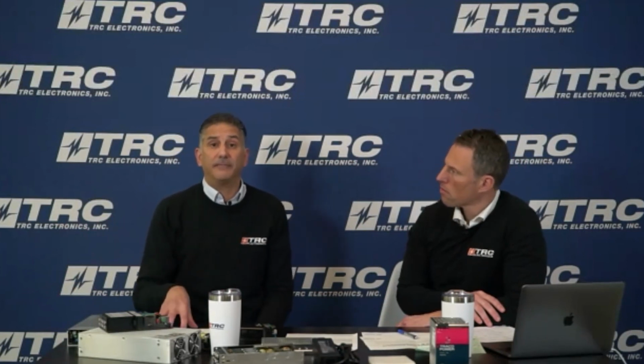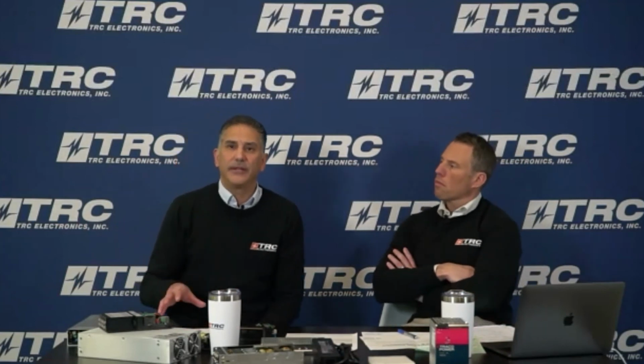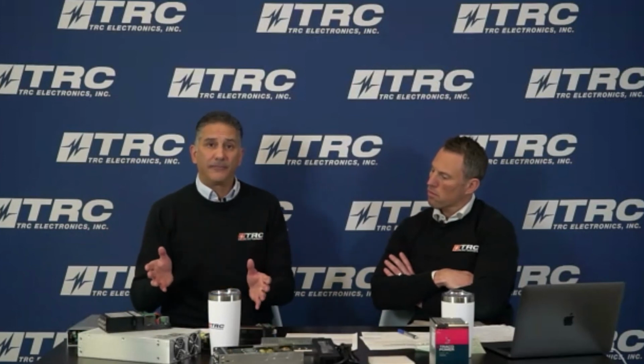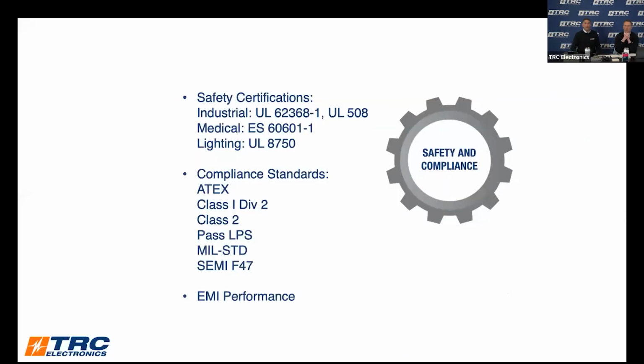And then we have Class number 2. Class number 2 is really a spec that comes off of UL 1310, which is commonly used in the lighting market where you want to protect the end user from any type of injury. What Class number 2 does is protect you from a voltage, a current, and overall power. Just speaking off the top of our heads, we remember it's 5 amps maximum, or 100 watts maximum, or 60 volts - these are the three parameters to meet a Class number 2.